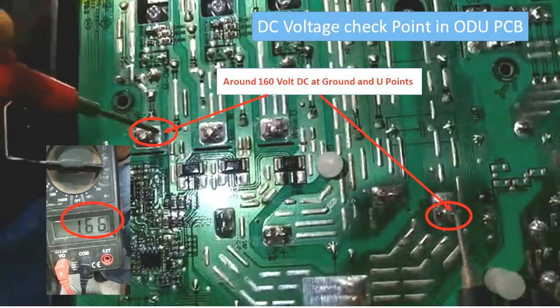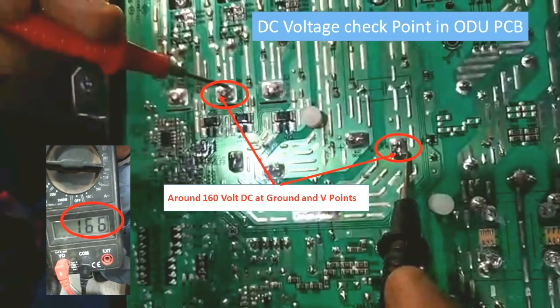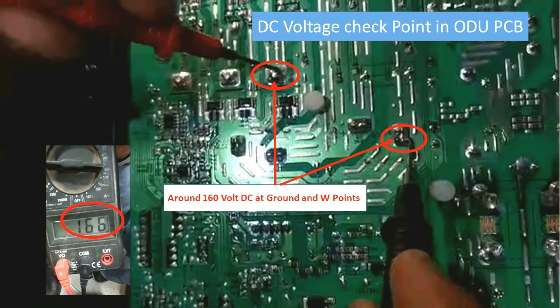For checking the IPM portion in the PCB, we can check AC or DC, both the voltages. For checking the DC voltages, we have to connect one probe to the ground terminal and the other to the U terminal. We will have 160 volt DC, and the same between V and ground point. Next, we will check the W terminal. Between W and ground, it should be the same as we get in both other terminals, 160 volt DC. If it is available, then the PCB is okay and the voltage supply is going to the compressor.